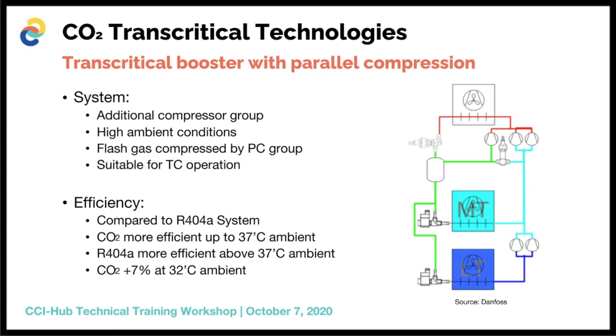Because operating in a transcritical mode, you can expect that after your high pressure valve, up to 40 to 50% of the mass flow of the refrigerant going through your high pressure valve will be vapor at the end of the day, and 50 to 60% would be liquid that can be used for cooling purposes. So this technology has made CO2 more feasible and suitable for transcritical operation, and therefore also a more suitable solution for higher ambient conditions. Comparing again to R404A, it has been found that this type of system gives you the capability of being efficient up to ambient conditions of 37 degrees Celsius, which is quite a high temperature and does cater for predominantly most of the countries around the world.